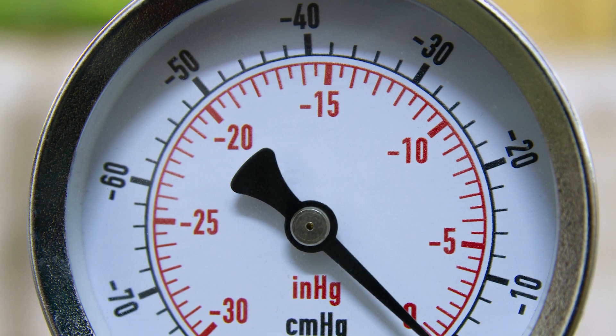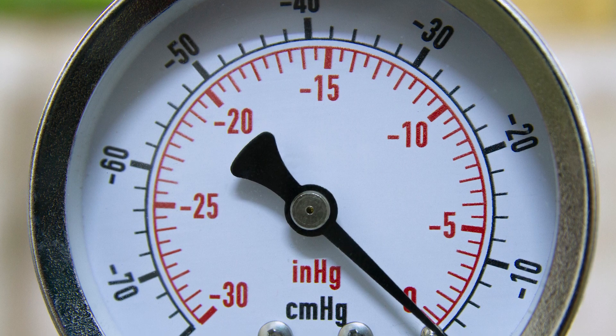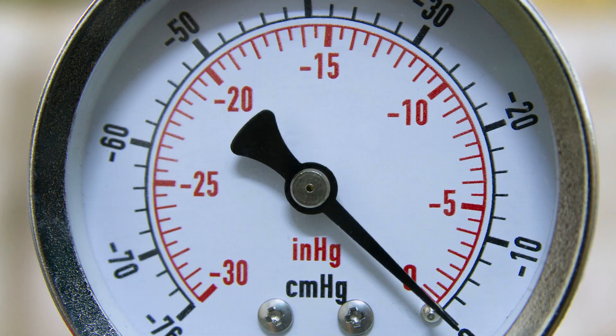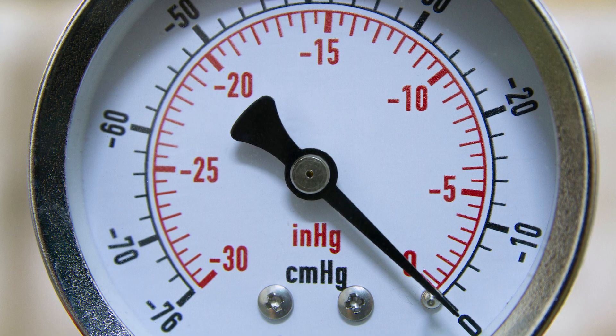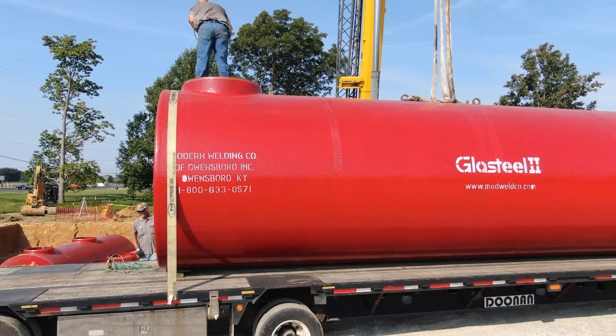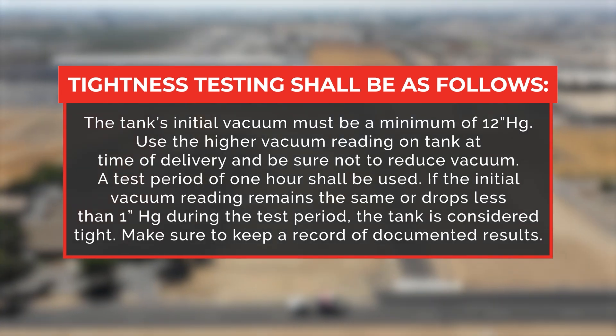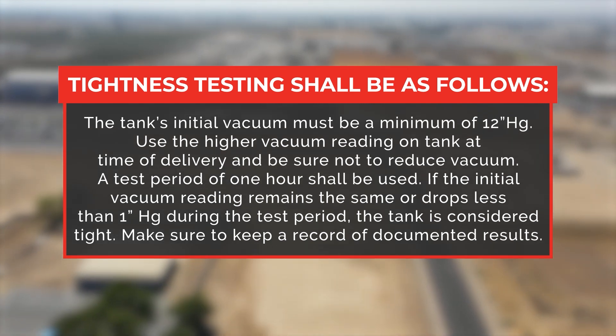Installers and owners shall note and document the tank's interstitial vacuum at the time of delivery to satisfy tank tightness requirements. Installers and owners should leave the vacuum and vacuum gauge assembly on the tank to monitor for possible damage during the installation process. If the interstitial vacuum level changes, investigate and contact the tank manufacturer. Glasteel II tanks are shipped with a vacuum gauge assembly which shows the amount of vacuum within the tank's annular space. The tank's initial vacuum must be a minimum of 12 inches of mercury.